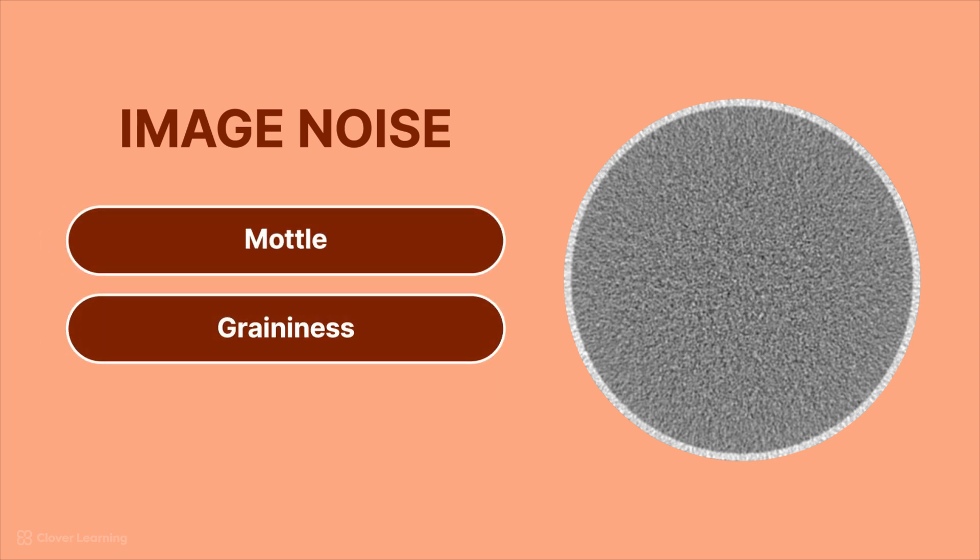Another quality control test that has to be performed on a regular basis is image noise. Image noise in CT is similar to image noise in radiography. It's basically the same thing as mottle or graininess in the image, and it's usually the result of significant attenuation of the x-ray beam.